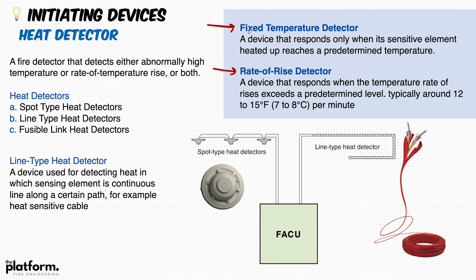The first is the fixed temperature detector, which responds only when its sensitive element reaches a predetermined temperature — for example 58 degrees or whatever other set value. The second type is the rate of rise detector, which responds when the temperature rate of rise exceeds a predetermined level, typically around 12 to 15 Fahrenheit degrees or 7 to 8 Celsius degrees per minute.